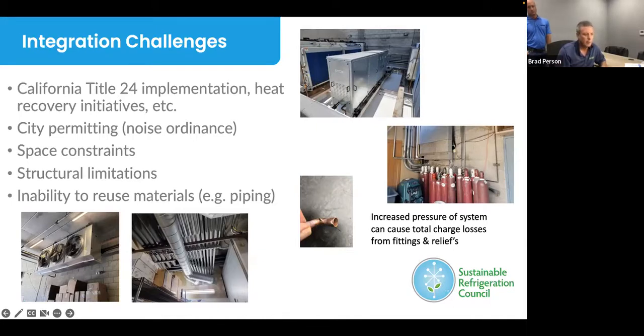I have a slide of a fitting that gave us an issue overnight at the Petaluma store. It uses completely different materials and operates at significantly higher pressure. When you plan for these systems, you have to mitigate the fact that you'll have more of these items fail, or a power outage that burps the system or vents the reliefs when pressures get too high, requiring a recharge.